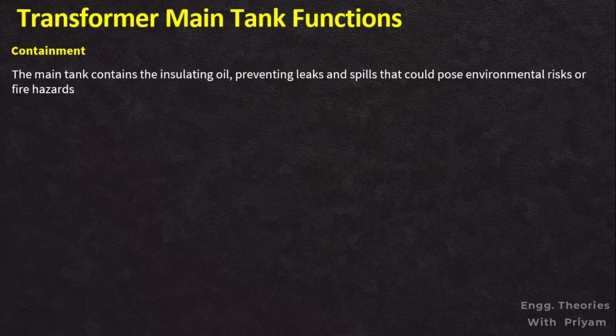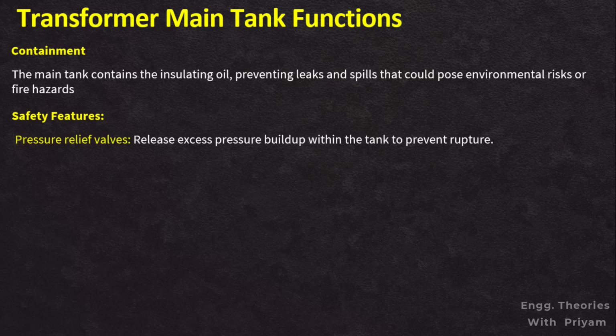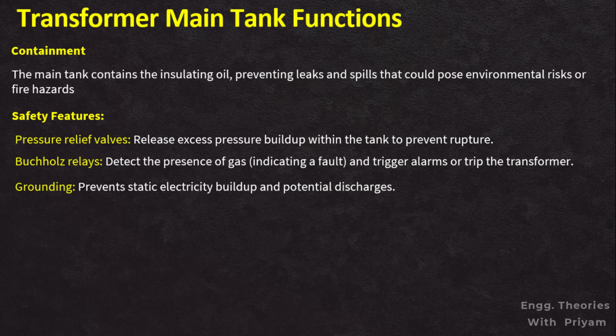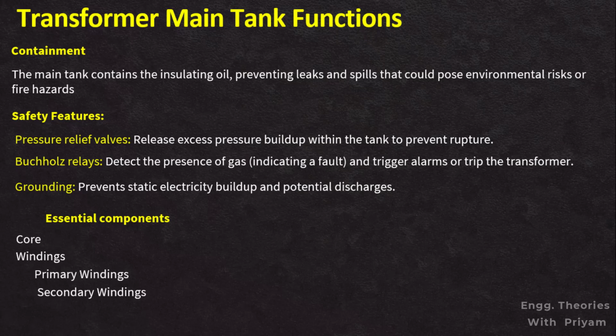Containment. The main tank contains the insulating oil, which prevents leaking and spills that could pose environmental risk or safety hazards. Safety features. The main tank often incorporates safety features like pressure relief valves, Buchholz relay, and grounding for preventing pressure buildup, detecting presence of gas, and also for preventing static voltage buildup and potential discharges. There are some essential components inside the main tank that are installed irrespective of application and voltage range. They are core and windings. There are basically three types of windings, which are primary winding, secondary winding, and tertiary winding, and transformer oil and insulation materials.